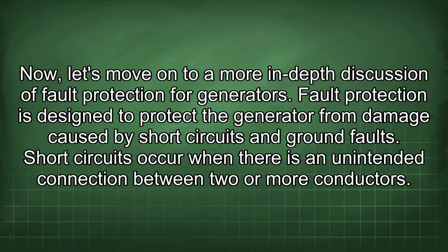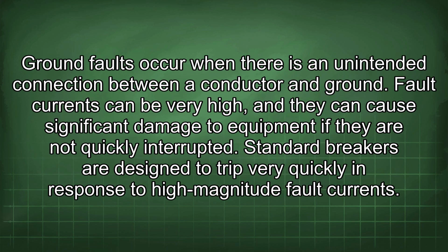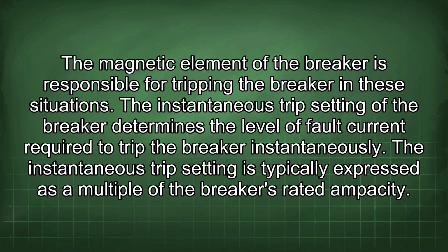Fault protection is designed to protect the generator from damage caused by short circuits and ground faults. Short circuits occur when there is an unintended connection between two or more conductors. Ground faults occur when there is an unintended connection between a conductor and ground. Fault currents can be very high, and they can cause significant damage to equipment if they are not quickly interrupted. Standard breakers are designed to trip very quickly in response to high-magnitude fault currents. A magnetic element of the breaker is responsible for tripping the breaker in these situations.